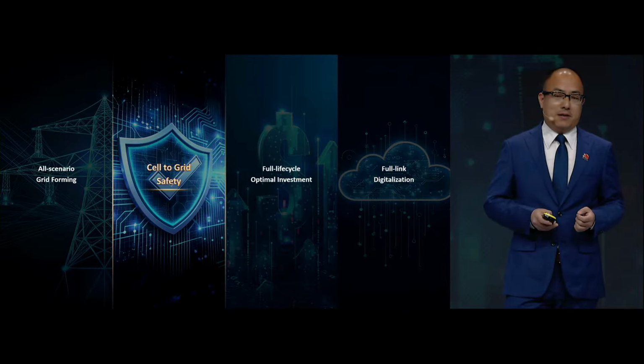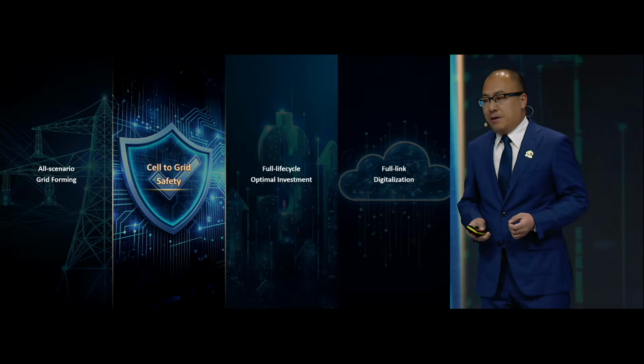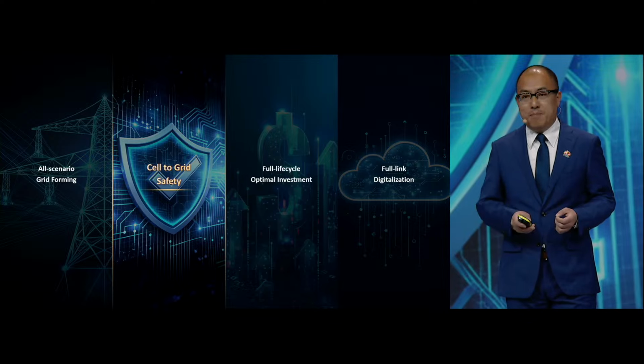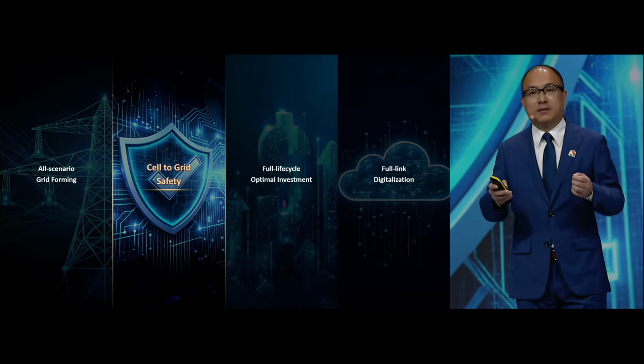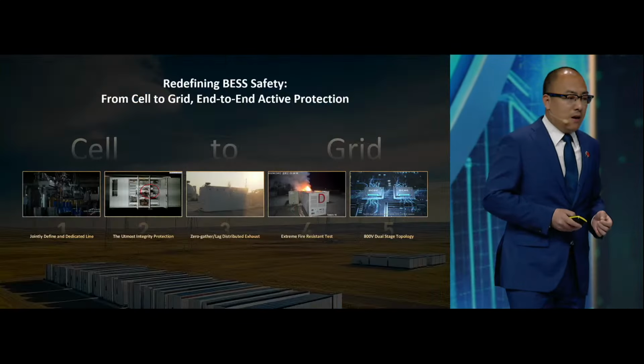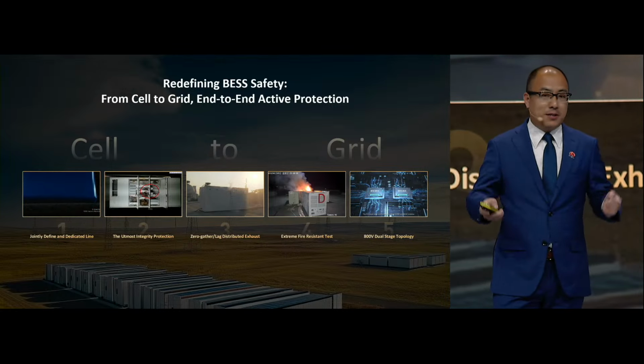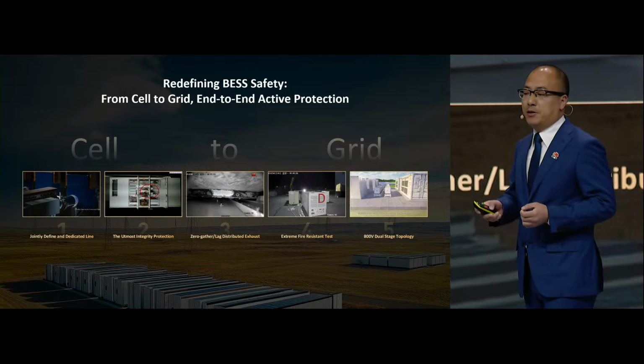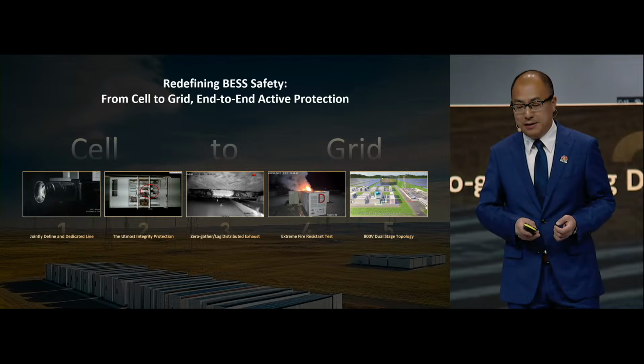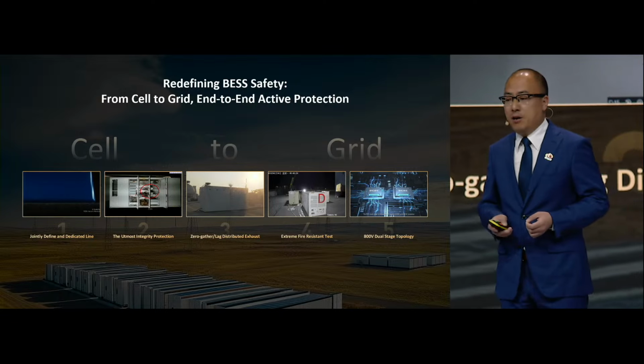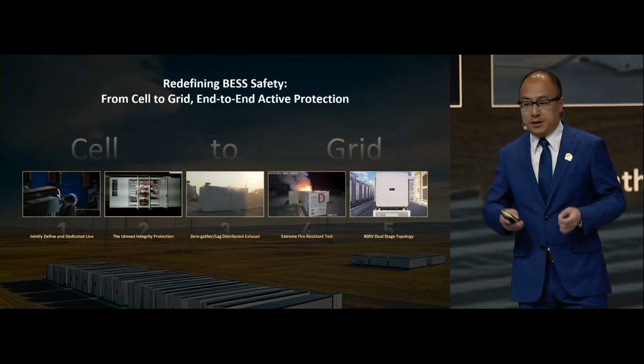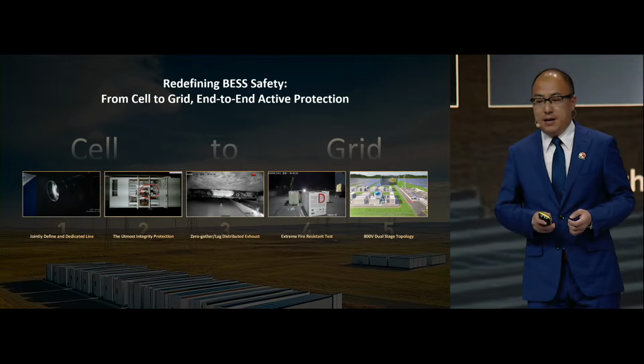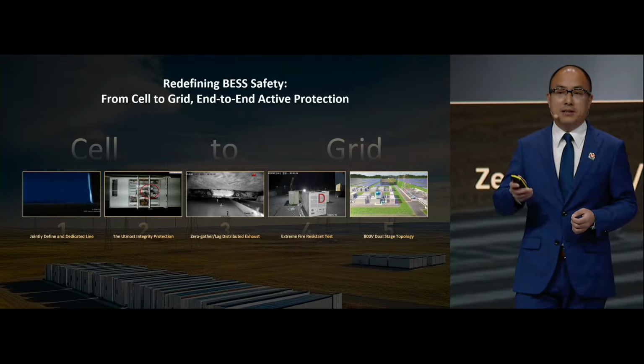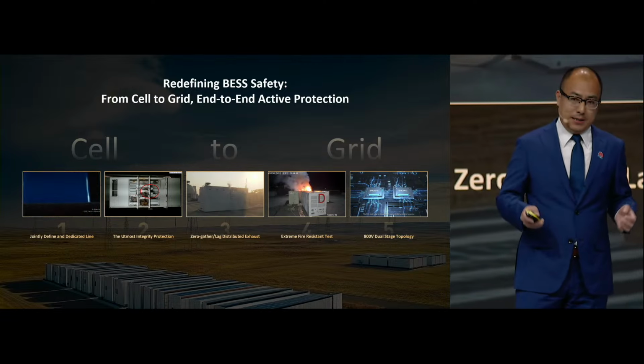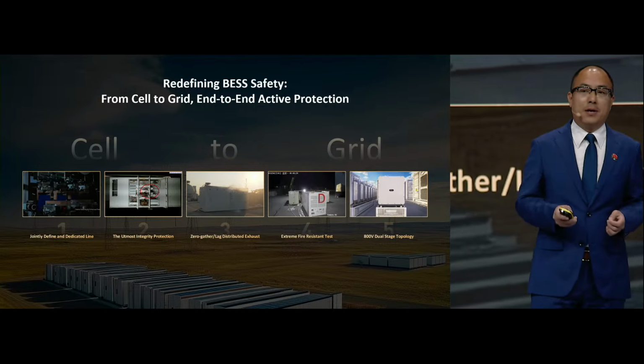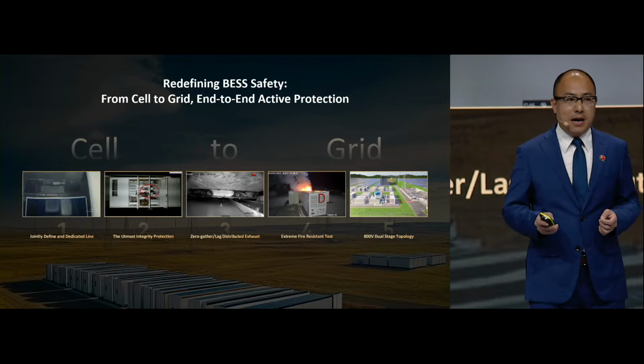Secondly, BESS foundation is safety. However, BESS safety is not only about the cell safety, but also includes pack, rack, container, and grid safety. First of all, for the cell, Huawei does not produce the cell, but we jointly define the Huawei cell with the supplier and build a dedicated production line with more than 1,000 control points and adopted aerospace-grade inspection standard. It is 10 times stricter than that in the industry. The process capability index, CPK, can reach 1.67, which is at the A+ level in the industry.